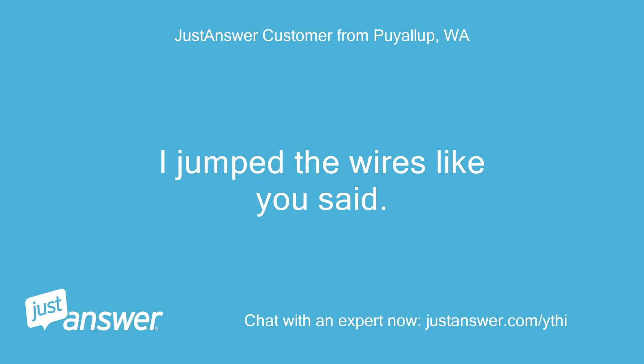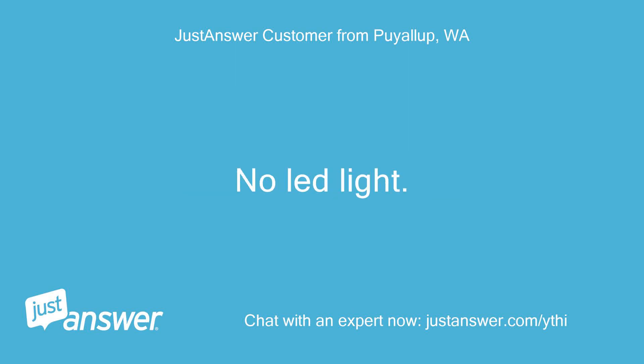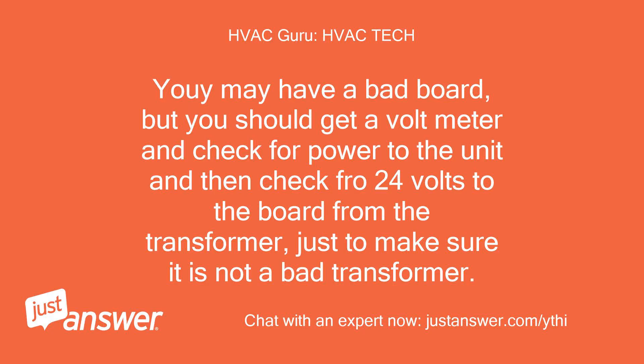I jumped the wires like you said. Nothing happened. No LED light. When they changed the fuse they used a 10 amp. You may have a bad board, but you should get a voltmeter and check for power to the unit and then check for 24 volts to the board from the transformer, just to make sure it is not a bad transformer.